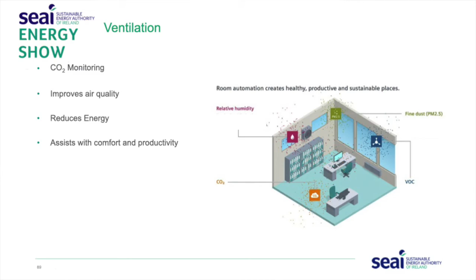In terms of CO2 and ventilation efficiencies, we try to use what we've got. Nearly every building we've done in the last few years has put in CO2 sensors in commonly occupied areas as part of a LEED program or a WELL program. But a lot of them just sit there with an alarm for a high level, and nothing really happens. We had a building we completed where Keith was involved in putting in CO2 sensors, using the ones already there with some additional dampers to manage the ventilation, spread it around, and ramp the AHU fans. All our AHUs tend to come with inverters anyway, so it's a case of managing that up and down.